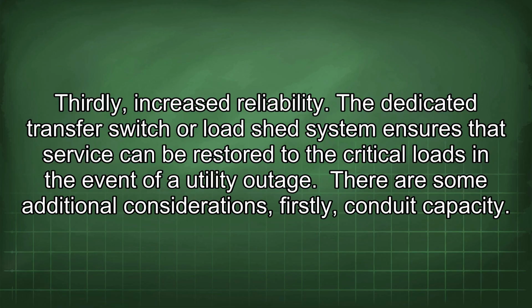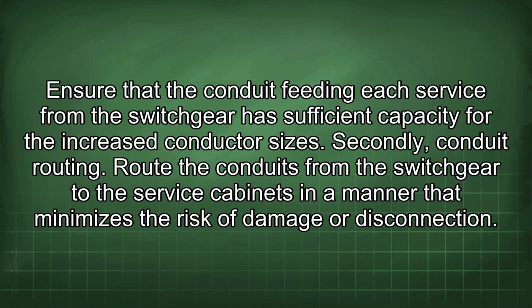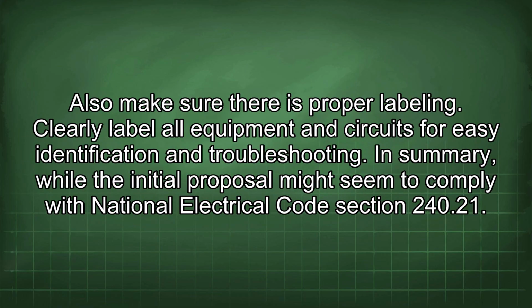There are some additional considerations. Firstly, conduit capacity. Ensure that the conduit feeding each service from the switchgear has sufficient capacity for the increased conductor sizes. Secondly, conduit routing. Route the conduits from the switchgear to the service cabinets in a manner that minimizes the risk of damage or disconnection. Also make sure there is proper labeling. Clearly label all equipment and circuits for easy identification and troubleshooting.